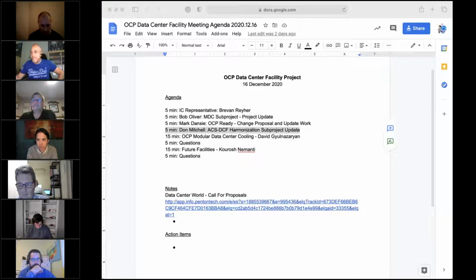So there's a longer discussion we should have in more detail, because the whole point of the non-condensing verbiage in the ASHRAE spec is precisely for this reason. I agree this is a somewhat different use case than what ASHRAE has typically dealt with, but I'm not sure you need an explicit dew point specification, because ultimately it's a complex interaction between the relative humidity in the data center and the temperature the liquid is actually at, as well as ambient temperatures and so on. I think we should have a longer discussion about it—I'm not sure you need an explicit definition.